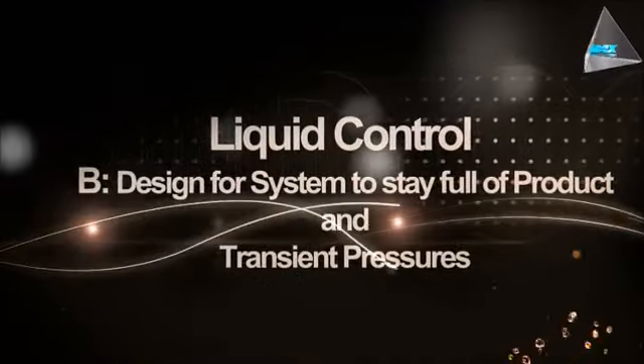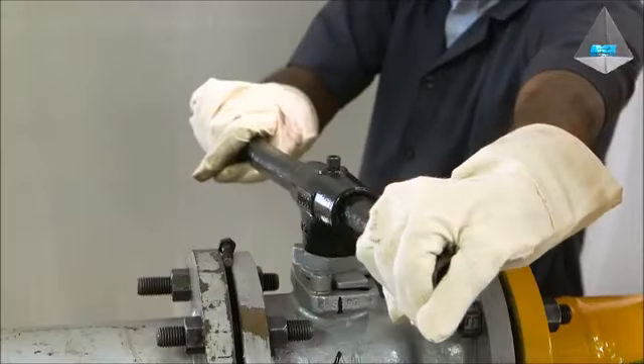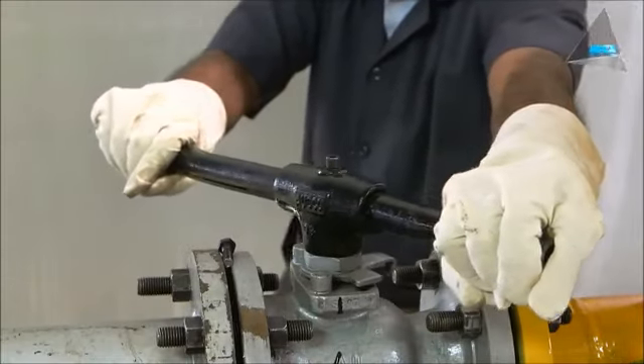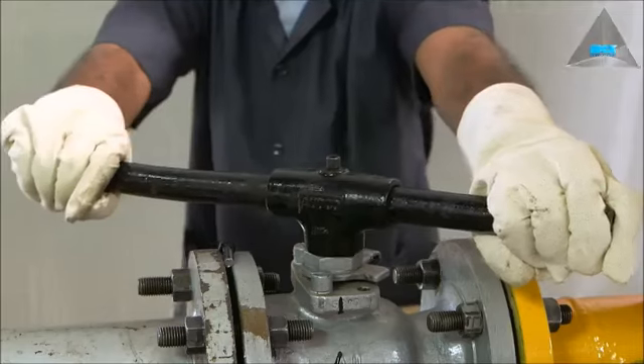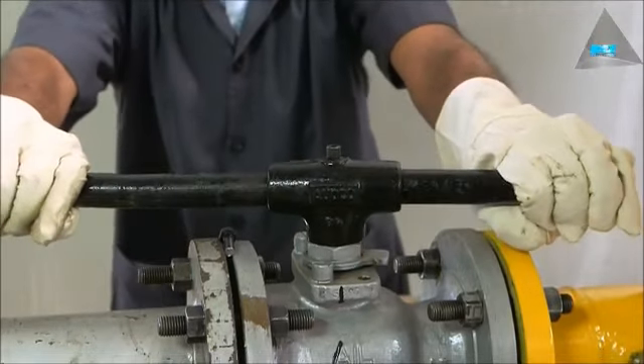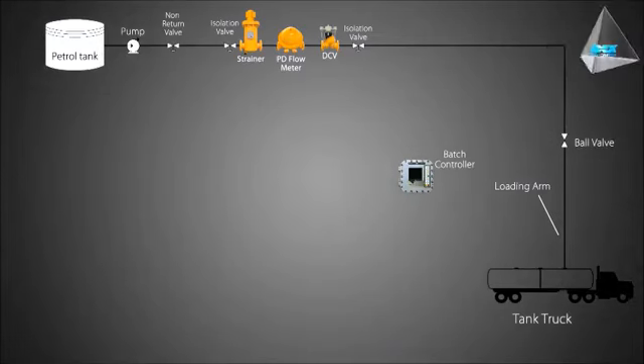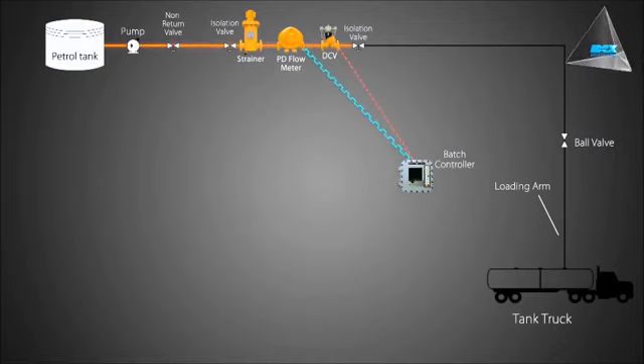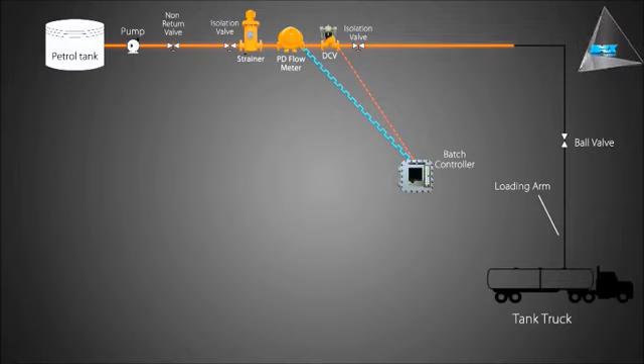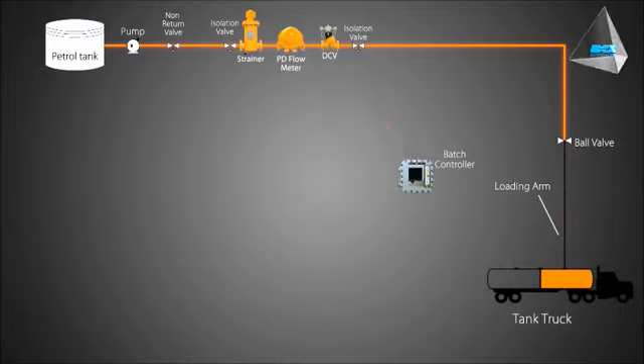The filling of the system must take place slowly to avoid spikes or transients caused by rapid acceleration or deceleration of the product. The system is to be designed to make sure that a positive head condition will always prevail in the system. Prevention of air entering the system and prevention of vapor generation within the system is a key factor in ensuring the accuracy and repeatability of the measurements.